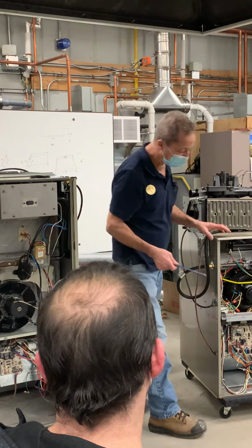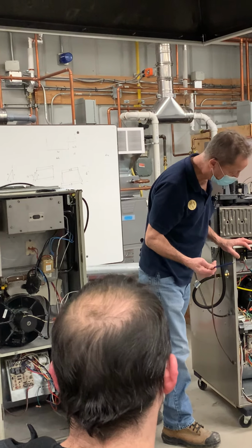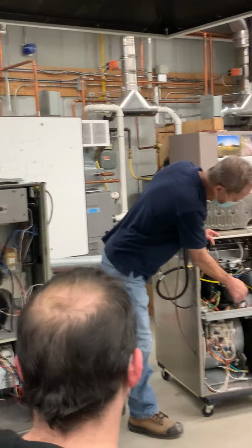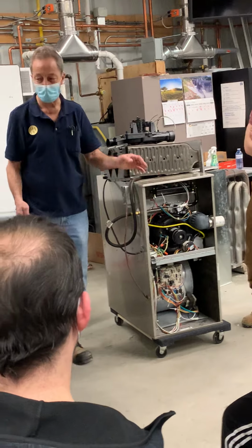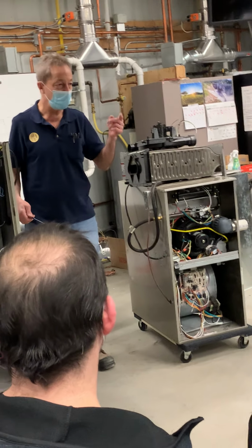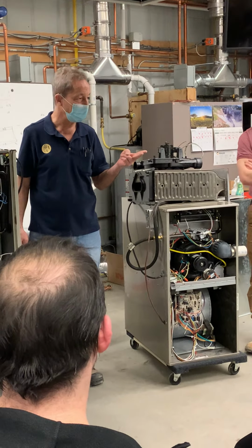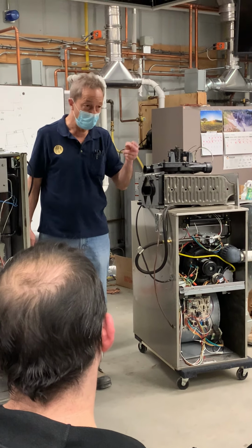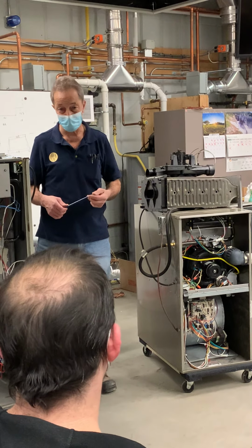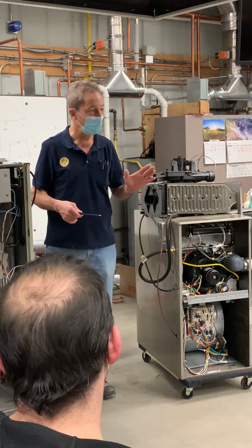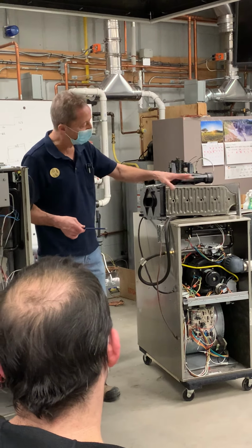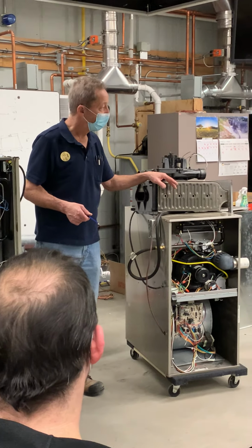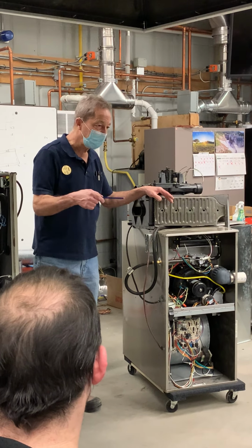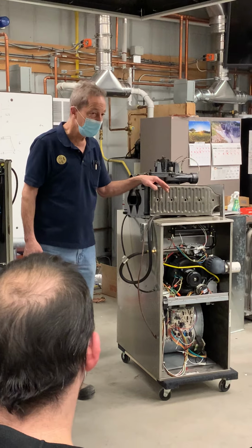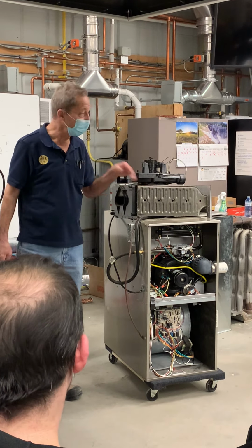So the net result is this. You get your digital manometer, and you guys will do this later, hook up to the hose over here. You're gonna see that it's gonna suck -2 to -3 inches water column. So it's more than it is on a mid-efficiency. So it's sucking harder. If the heat exchanger is blocked, what do you think is gonna happen to that pressure? Is it gonna go more negative or less negative? It's gonna go more negative, isn't it?